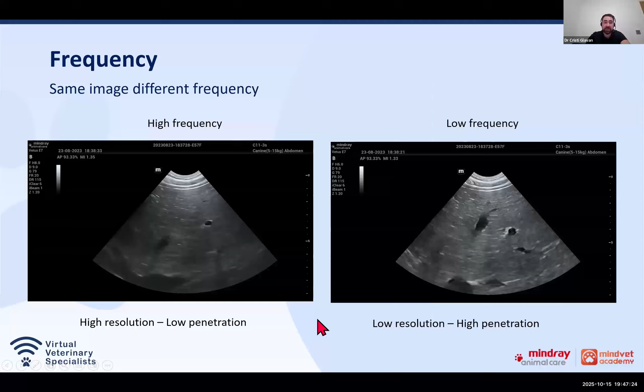Okay, so this is really dependent on frequency, and it's something that we always need to be aware of. One thing that is more important: I've heard some people confusing this terminology a bit. Depth and frequency are two distinct settings. They are connected, but they are separate settings. Frequency depends on the probe, and depth is a machine-dependent and user-dependent setting. We'll discuss this in the next slides, but I just want to make sure that we are emphasizing those points.